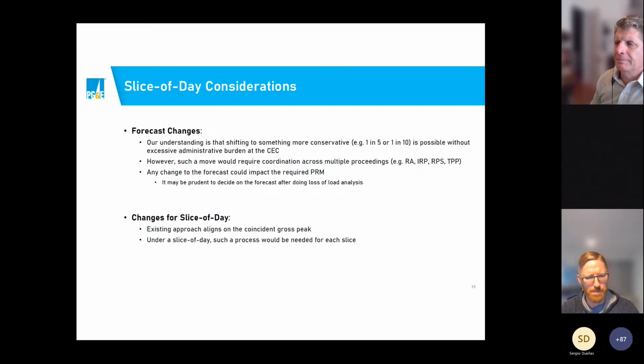I think just one point I would make here is that one issue that's emerging is that the tools we have, the production cost modeling for that loss of load analysis, are tied to normalized weather years that are based on 30 years of actual weather data. One thing we tend to see from the modeling is an underestimation of climate trends.